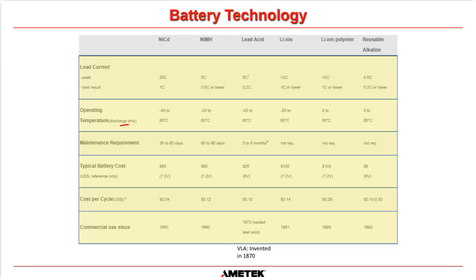Operating temperatures, this is discharge only. I think this is kind of an ambiguous value. For a NiCad, it says -40 to 60, and it's saying for a lead acid, -20 to 60 degrees C. I don't like this term discharge only, because in the majority of places where these batteries are going to be installed, they're going to be in float mode operation, and that's the operating temperature that they should be looking at.